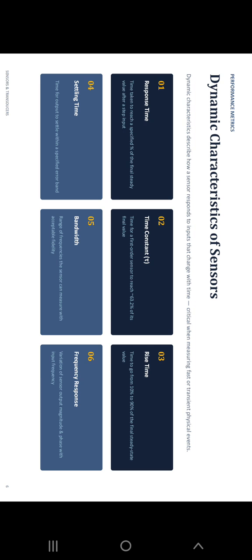Response time: time taken to reach a specified percentage of the final steady value after a step input. Time constant: time for a first order sensor to reach 63.2% of its final value. Rise time: time to go from 10 to 90 percent of the final steady value. Settling time: time for output to settle within a specified error band. Bandwidth: range of frequencies the sensor can measure with acceptable fidelity. Frequency response: variation of sensor output magnitude and phase with the input frequency.